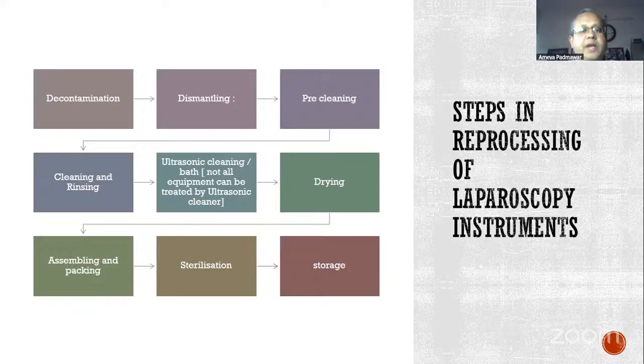You have to dismantle them. So when you're choosing your instruments, you should choose instruments which can be dismantled easily. If you cannot open these slender, lean, coaxial instruments, it is difficult to get rid of all the biological material, and it is going to have an impact on your subsequent cases. Then comes the step of pre-cleaning, followed by cleaning and rinsing of the instruments.